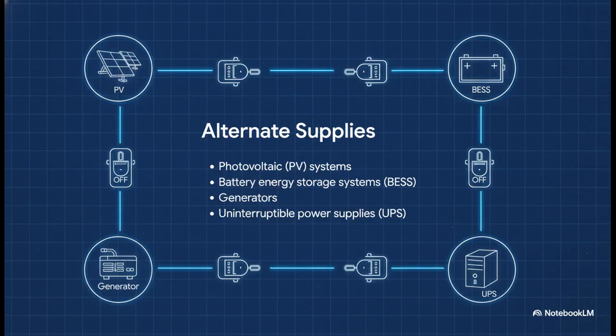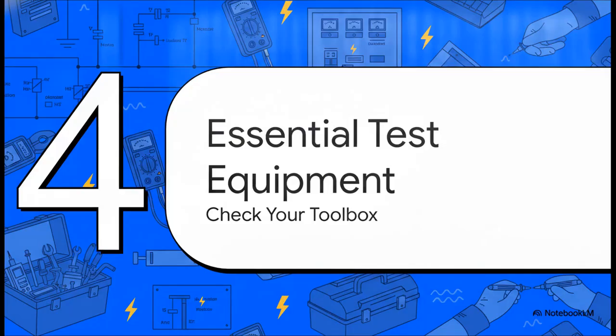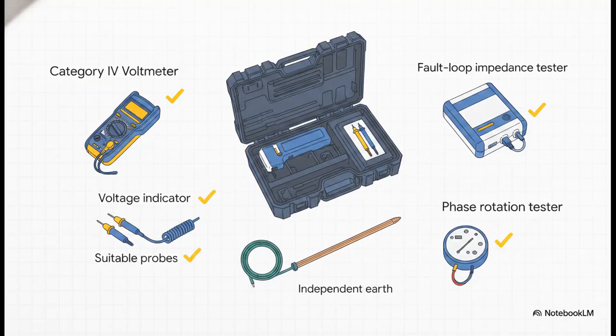No exceptions. Section 4, essential safe test equipment. Before you even think about touching a switchboard, we need a strict, uncompromising check of the toolbox. Because we're testing on low-impedance sources, a Category 4 voltmeter and proper test probes are an absolute must. You're also going to need a voltage indicator, a fault loop impedance tester, a phase rotation tester for your three-phase systems, and crucially, a solid way to make an independent earth connection. And please, remember the golden rule of test gear: always verify the correct operation of your devices both before and after use. Don't let a busted meter be the reason things go south.